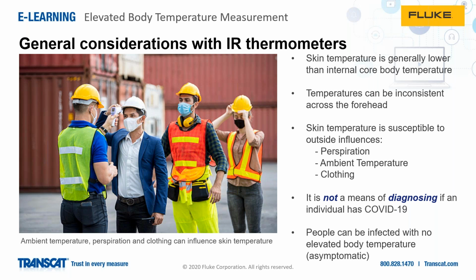I'm sure for anyone who's on the line here that's used an IR thermometer, you may get some variability across the forehead, and it's just not necessarily a consistent temperature across the forehead for every individual. And this could be related to what we talked about before, which is that skin temperature is susceptible to outside influences. These outside influences include perspiration from exercise, ambient temperatures, whether they be hot or cold, as well as clothing or hair, maybe that's across the forehead while you're being screened.